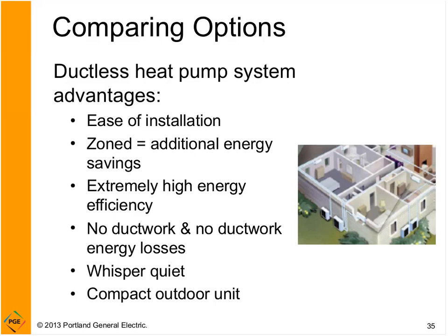So some of the advantages of ductless heat pumps: ease of installation. They go in very quickly without really having to have the tenant be out of the space for very long or anything like that. In fact, they could probably be around. If it's zoned, there are additional energy savings in larger spaces that would require zoning.